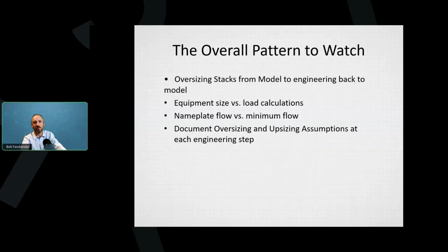Okay, so I'm going to get to a little checklist for the field in a minute, but the overall pattern here is that you run the model, oversizing stacks into modeling, and then it goes into engineering and back into the model. The equipment size is a lot bigger than the load calculations as a result of the previous bullet point. We want to check the nameplate flow versus minimum flow if we can. And the biggest takeaway from all of that is that you want to document oversizing and upsizing assumptions at every step.